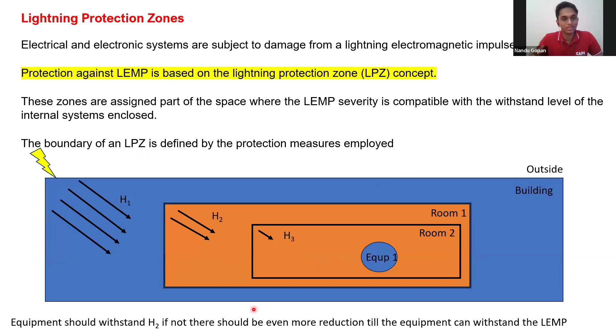And if you are asking me how H1 reduces to H2 and H3, I will explain in these slides what protective measures can be employed at the boundary of LPZ so that this reduction happens. This is just one example, just magnetic field strength. There can also be a lightning current, lightning impulse, which can come inside this equipment if there is any line going outside this equipment, room, or building. So this is the basic concept.